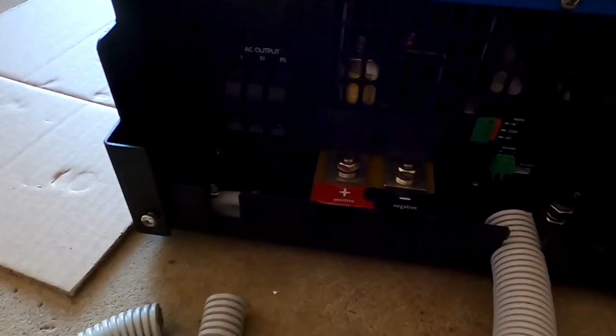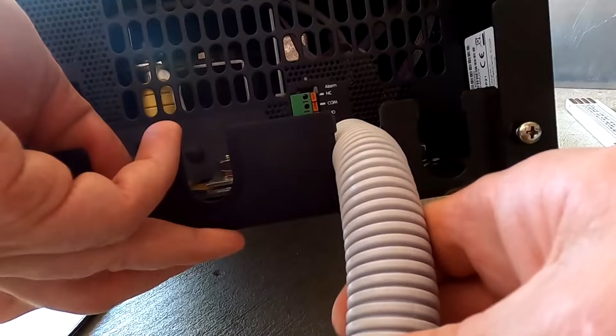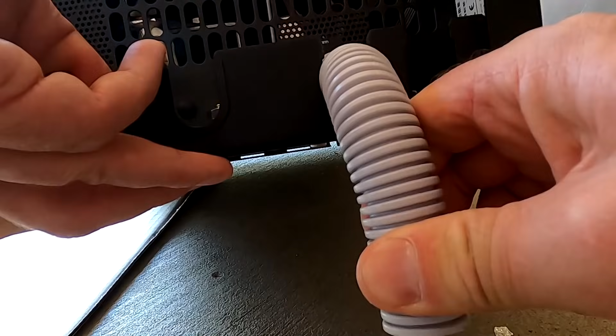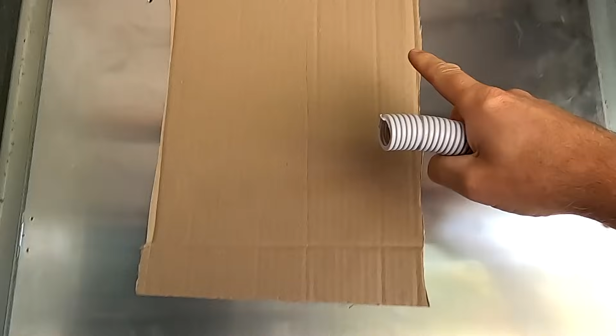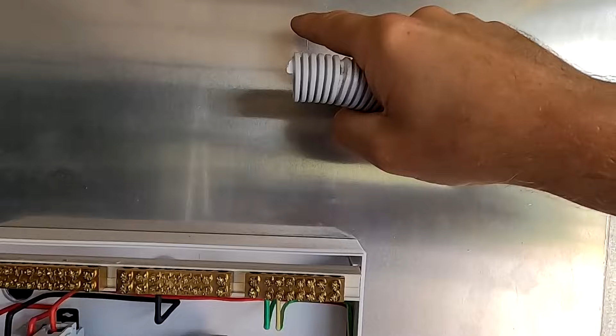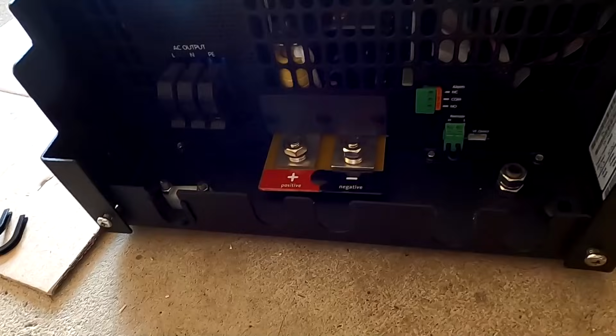And this is really solid, you know. And then the plan is, let me show you here. So the plan is to have these conduits bent like this, so they're going back into the wall just under the connection terminals of the inverter. If this is our inverter, basically they are coming out of the inverter and then bending down straight away. I drill a hole here and they go behind the aluminium plate, and then I can wire them up to the switchboard or to other connections in the system. Well, that's at least the plan. If this all works out, we will see today, soon. Then let's mount this inverter back on the wall. Right, Toby?